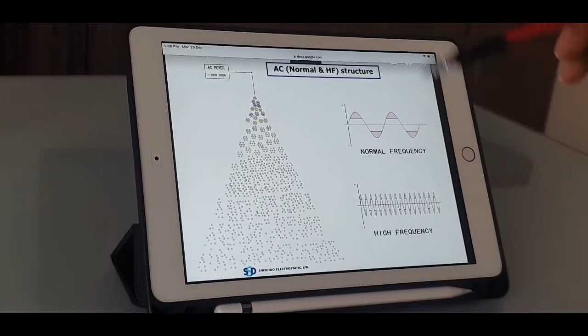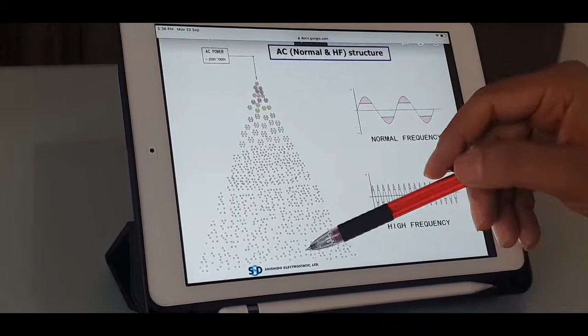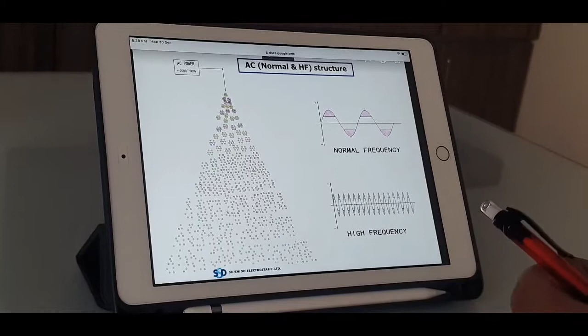Not like 50 hertz, but 68 kilohertz. Because of 68 kilohertz, they are able to generate the ions at 2 kV. They inject the power of 2 kV, and they are able to produce the ions. Then the corona discharge happens at a lower voltage. So 2 kV means less pressure on the needle, a single needle producing positive and negative ions, and they get the long-term balance.